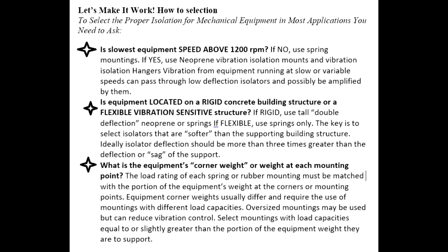To select the proper isolation for mechanical equipment in most applications, you need to ask: first, is the slowest equipment speed above 1200 rpm? If no, use spring mountings. If yes, then use neoprene vibration isolation mounts and vibration isolation hangers. Vibration from equipment running at slow or variable speeds can pass through low deflection isolators and possibly be amplified by them. Is the equipment located on a rigid concrete building structure or a flexible vibration sensitive structure? If rigid, use tall double deflection neoprene or spring. If flexible, use spring only. The key is to select isolators that are softer than the supporting building structure. Ideally, isolator deflection should be more than 3 times greater than the deflection or sag of the support.